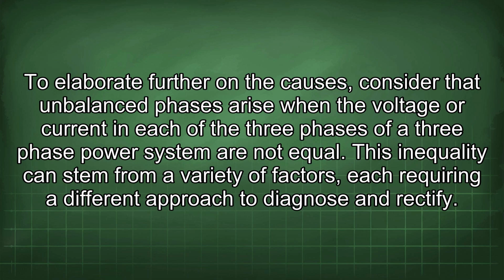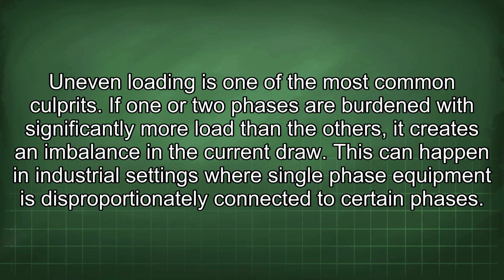To elaborate further on the causes, consider that unbalanced phases arise when the voltage or current in each of the three phases of a three-phase power system are not equal. This inequality can stem from a variety of factors, each requiring a different approach to diagnose and rectify. Uneven loading is one of the most common culprits. If one or two phases are burdened with significantly more load than the others, it creates an imbalance in the current draw. This can happen in industrial settings where single-phase equipment is disproportionately connected to certain phases.